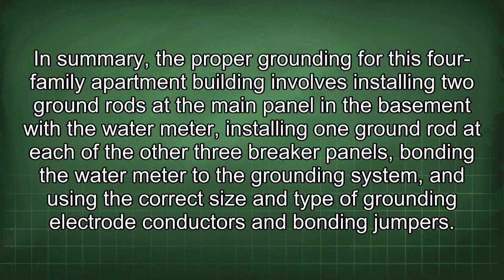In summary, the proper grounding for this 4-family apartment building involves installing 2 ground rods at the main panel in the basement with the water meter, installing 1 ground rod at each of the other 3 breaker panels, bonding the water meter to the grounding system, and using the correct size and type of grounding electrode conductors and bonding jumpers.